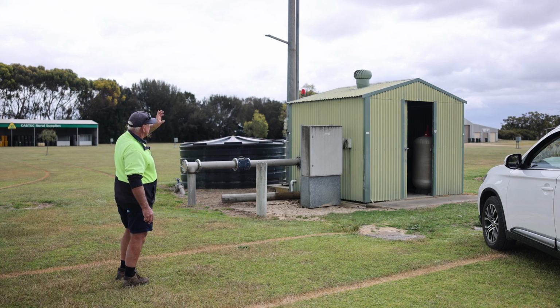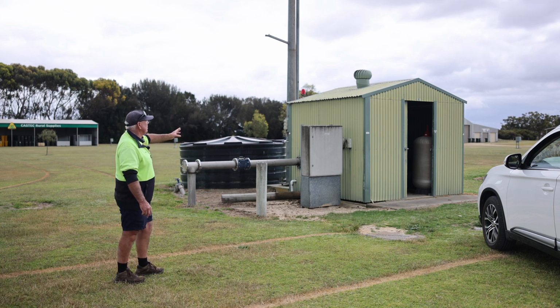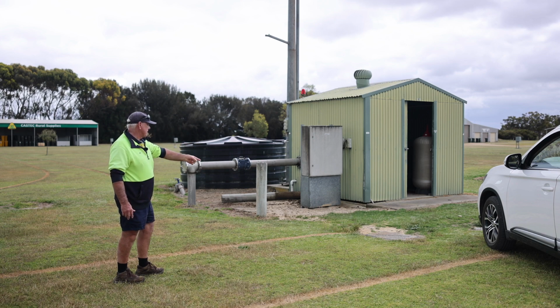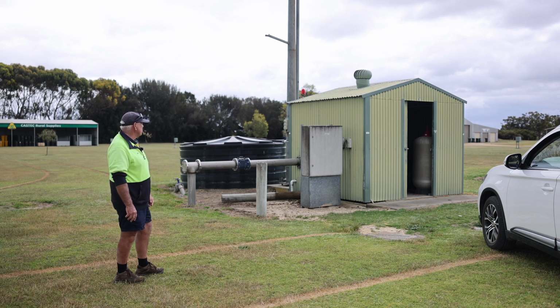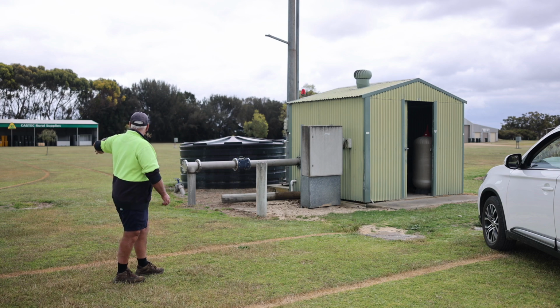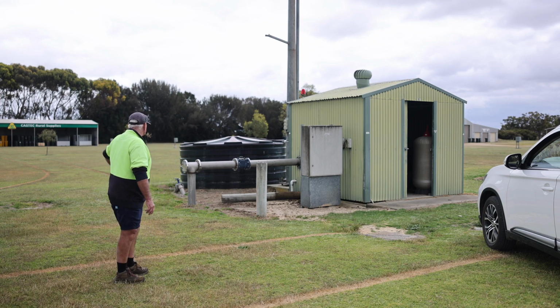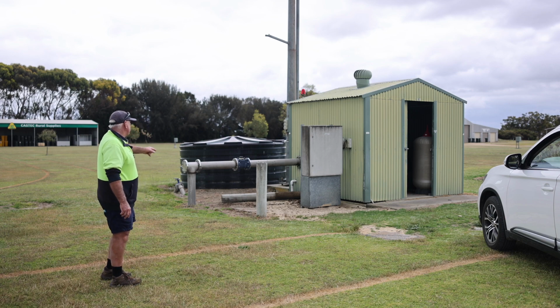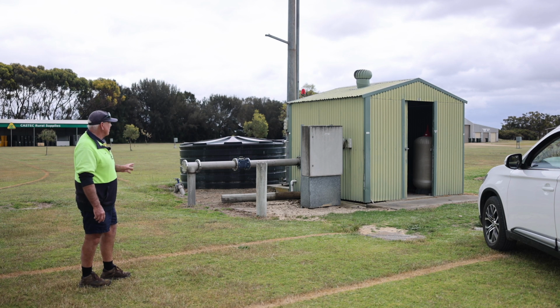And also that switchboard was disconnected from the mains and was run from this generator pit here, where there was a generator sitting over that. So virtually we disconnected from the mains, put half through that switchboard and one genset, and half from this genset. At times we have needed to move a couple of circuits over. That's why there's a cable going from behind back into this box.